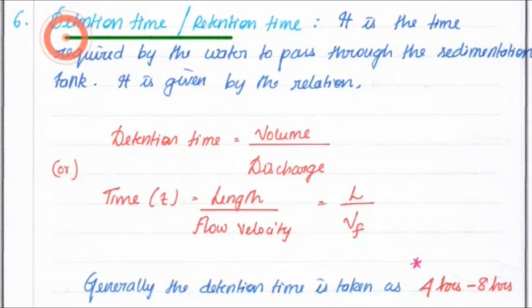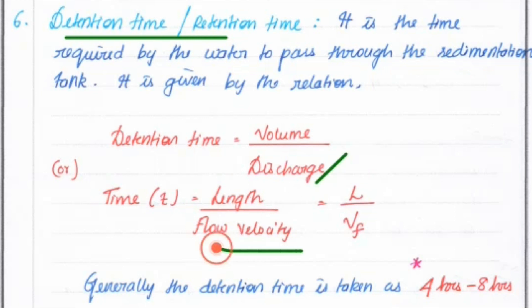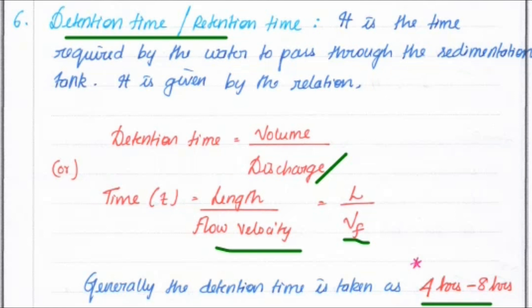The next important factor is detention time or retention period — the time required for water to pass through the sedimentation tank, or how long the water spends in the tank. It is given by: detention time = Volume / Discharge, and also time = Length / Flow velocity (VF). Generally, detention time is taken as 4 to 8 hours, based on how much treatment is required. The value of SOR is generally 12 to 18 cubic metres per day per square metre.